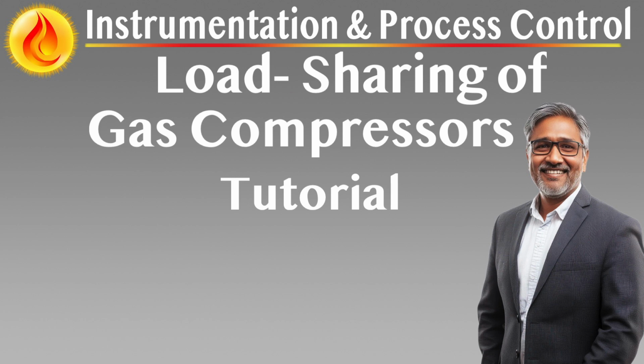Benefits of pressure override control. Stabilizes transients: absorbs sharp process shocks without full recycle engagement, prevents overpressure events, and avoids sudden shutdowns or safety valve actuations. Protects equipment integrity: limits pressure surges that could strain exchangers, piping, or downstream units. Enhances process control: supplements primary loops with predictive responsiveness. Maintains surge safety: always subordinates to anti-surge logic, avoiding control conflict.